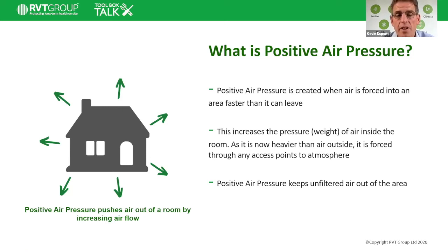How can we effectively stop that microscopic particulate migrating into these areas, which should be perfectly clean? These are breakout areas, they're safe areas. And it could be achieved so easily with positive pressure. So you'd have a fan outside in the work zone where the dust is, but put it through a filter, so you're filtering in under positive pressure into these clean areas. That would stop anything migrating in.